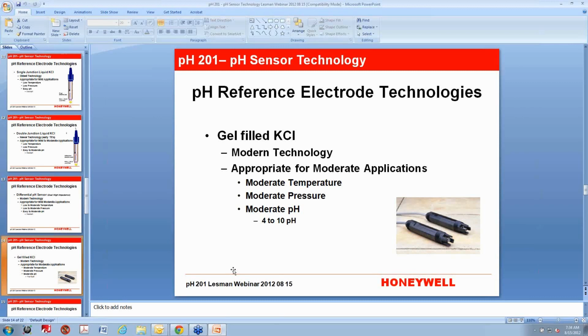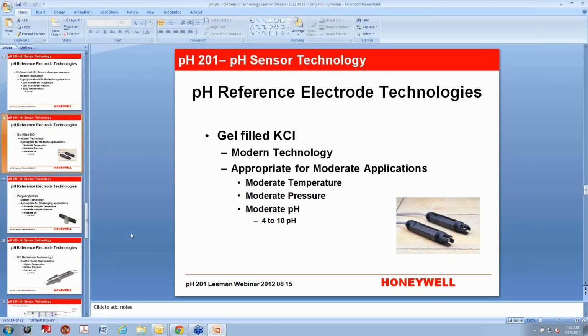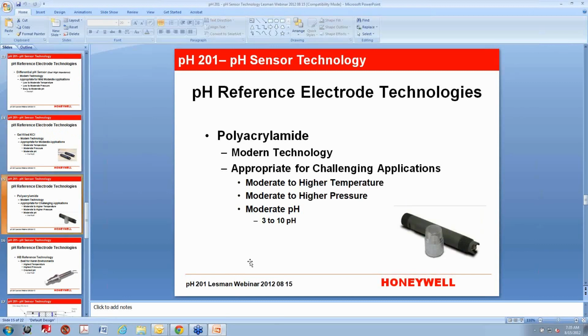Now, I've seen these put into applications that are less than 4 and greater than 10. It just depends on the chemistry as to what will work. But again, that's probably the most widely applied type of fill. Next one up is a polyacrylamide. There are a few manufacturers, small manufacturers, not what I'd call one of the giant ones like Honeywell, that manufacture polyacrylamide reference. It's a squishy, soft plastic. It reminds me of styrofoam, except it's really dense. And these are all still potassium chloride. This is just a different physical formulation.